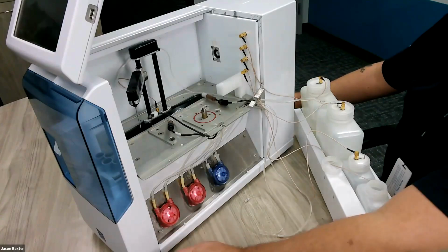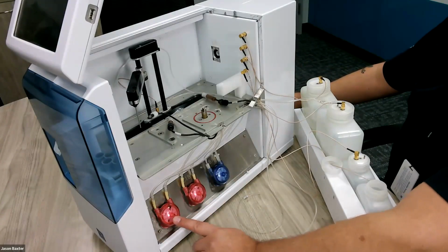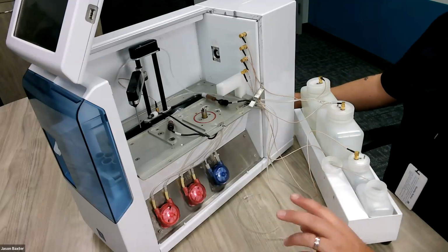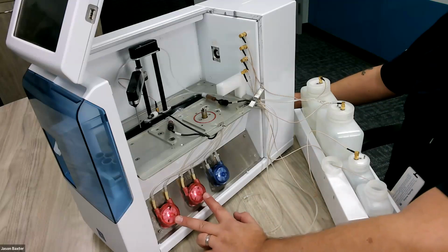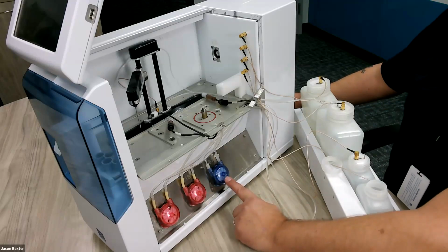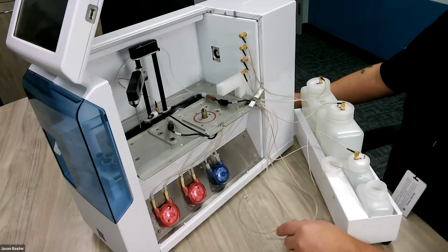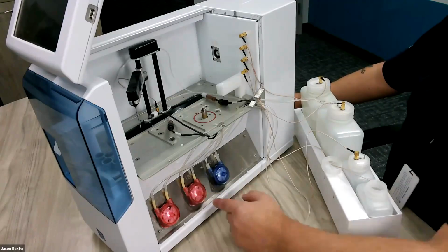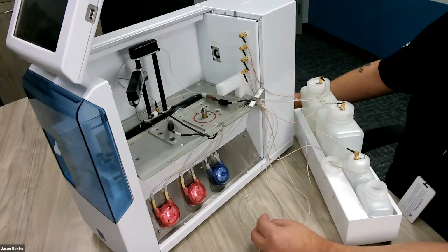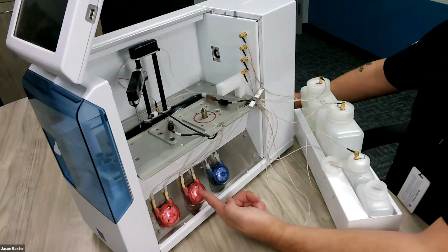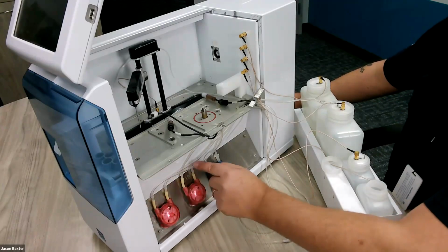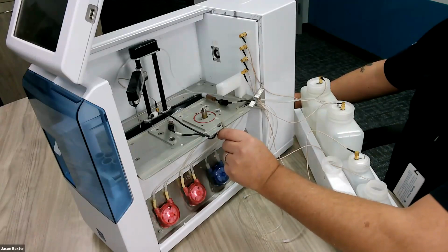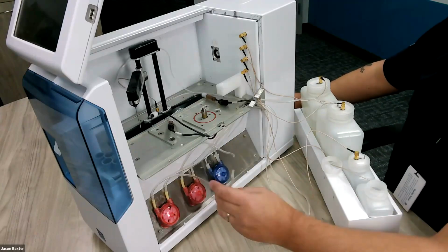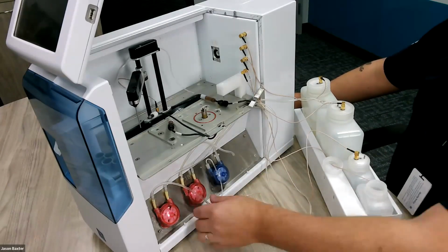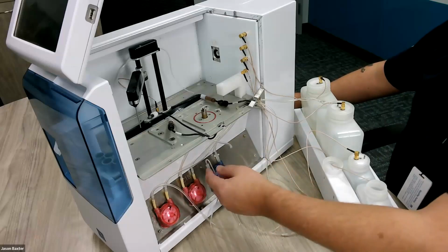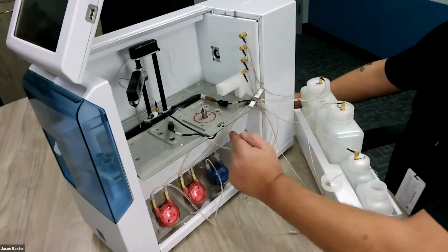So we can see, starting from here to here, we have calibrator 1A, calibrator 1B, and our buffer. You'll notice that the calibrators are a red color. The caps are identical between the two, and the buffer is blue. So it's very easy to remember, at least in my opinion it is. And if you follow, just to pick on calibrator 1A, you may remember from a moment ago, I said A is on the left, B is on the right. And if I follow my outlet tube up, that one is the one that plugged into the left-hand side port. So at this point, you can just draw your tubes down. So we should have 3 free ends right now. And then you can pull your other ends of your tubing through here.